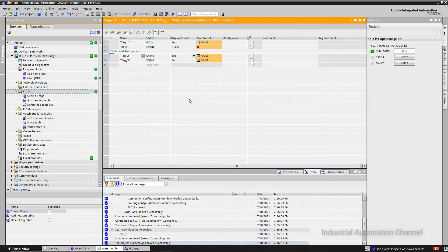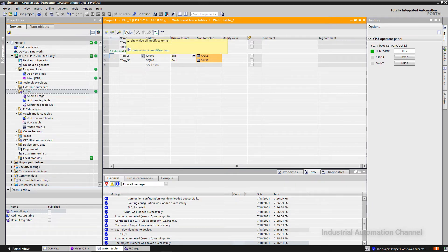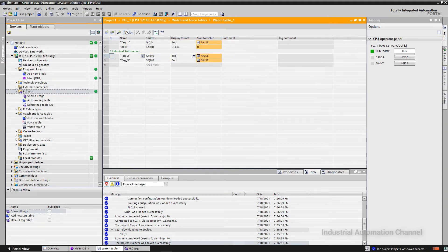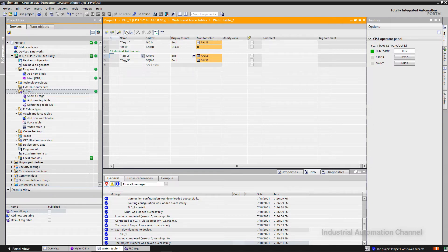When I change the program, a little orange symbol is added here. It means we have changed the program and need to download it again to the PLC. Once downloaded, everything is again green. Next, another thing we can do with the watch table is changing IOs — in other words, modifying tags of inputs and outputs. You can see the 'show/hide all modify' option on top. By default it is activated; if you click on it, it will be deactivated and you can only monitor your inputs and outputs.